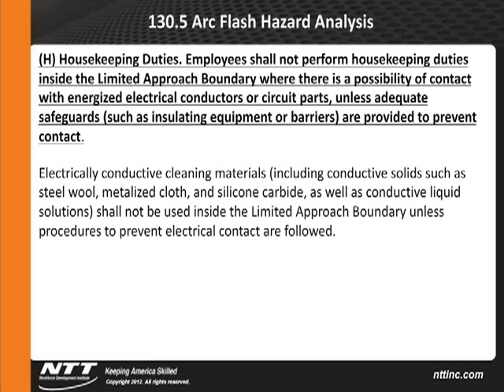It's been further clarified: limited approach boundary. Remember, the limited approach boundary is when you've got an exposed part and piece. Electrically conductive cleaning materials, including conductive solids such as steel wool, metallized cloth, and silicon carbide, as well as conductive liquid solutions, shall not be used inside the limited approach boundary unless procedures to prevent electrical contact are followed. Again, folks, we've got to train our people. What can you use? What can't you use?